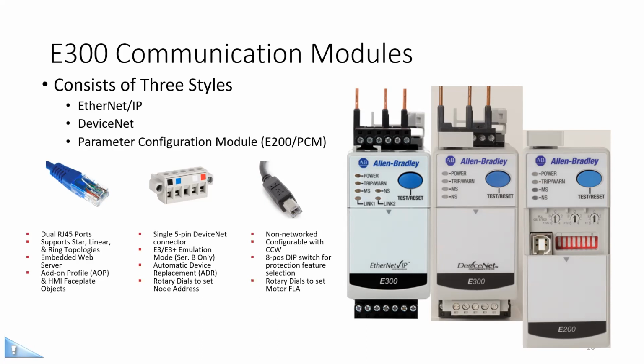All communication modules have diagnostic LEDs to aid the user when diagnosing an event. There's a power, which indicates the protection state of the E300 trip or warn, and the module status and the network status. There's also a blue reset test button to do a reset, which is in the same XY panel position as the E3 Plus. So there wasn't any changes needed. There's a cover. You can see it sliding down on the E200. Underneath that cover, you'll see the rotary dials and the dip switches, because all the communication-based modules can set their network node address using these rotary dials.